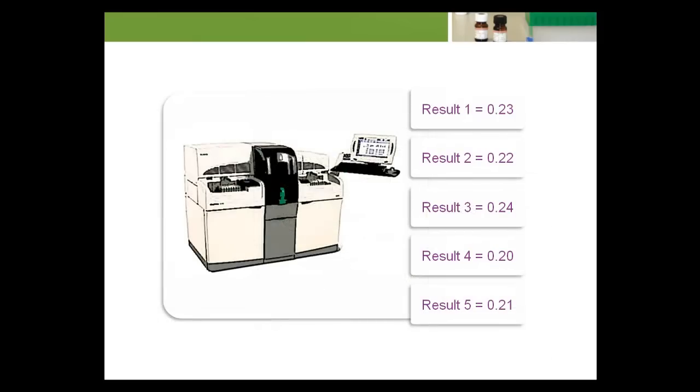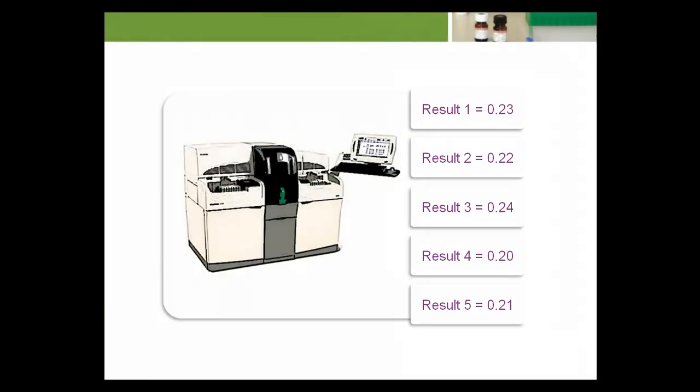Each time an analytical module produces a result, that result contains a certain amount of random measurement error. This random measurement error can make the result higher or lower than it should be, so that if the same specimen is analyzed multiple times, multiple results are produced. The variation in results between multiple evaluations of the same specimen is a function of the analytical imprecision of the module that can be quantified by computing the coefficient of variation, or CVA, of the module.